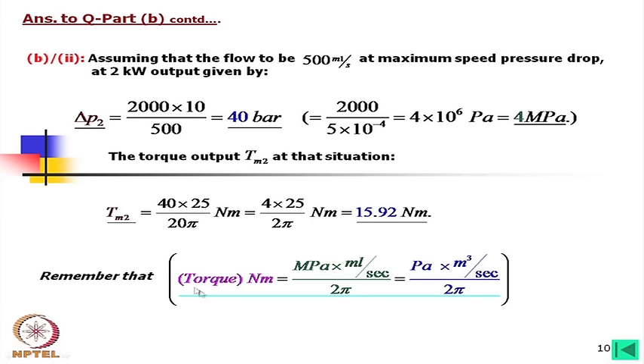Remember: torque in Newton meters = megapascals × milliliters per revolution ÷ (2π), because the 10⁻⁶ from megapascals to Pascals and the 10⁻⁶ from milliliters to cubic meters cancel each other out. It is better to remember this relation for calculations.